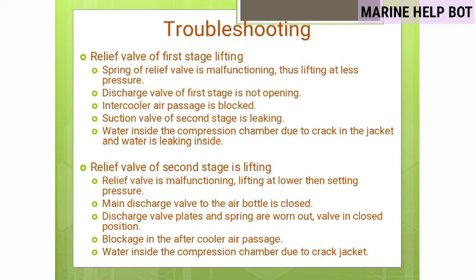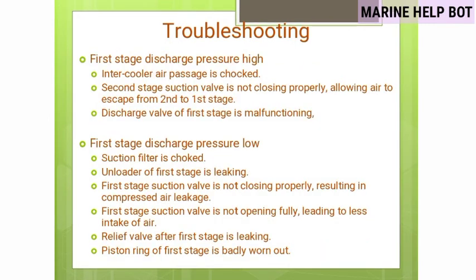Why is the second stage relief valve lifting? Causes include: relief valve malfunctioning and lifting below setting pressure; main discharge valve to the air bottle is closed so air is not going to the receiver; discharge valve plate and spring are worn out and the valve is in closed position; blockage in the aftercooler air passage; or water inside the compression chamber due to a crack in the jacket causing incompressible high pressure.